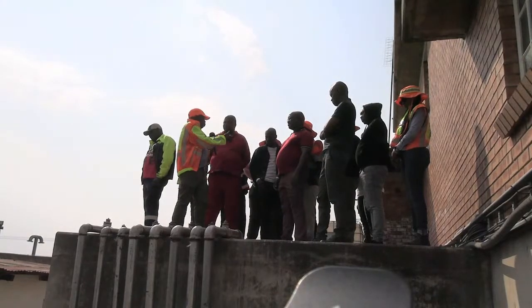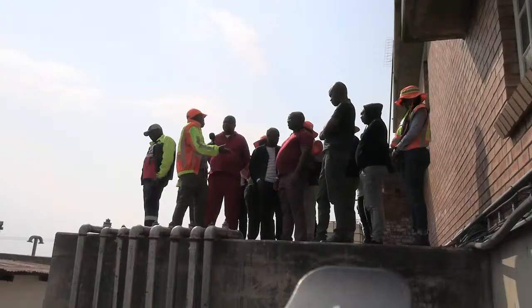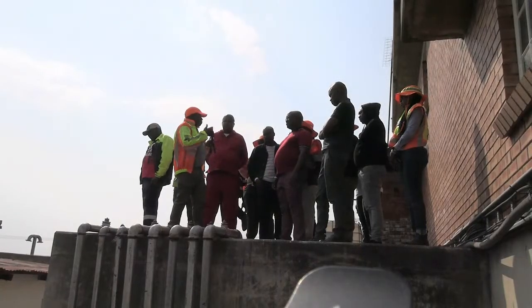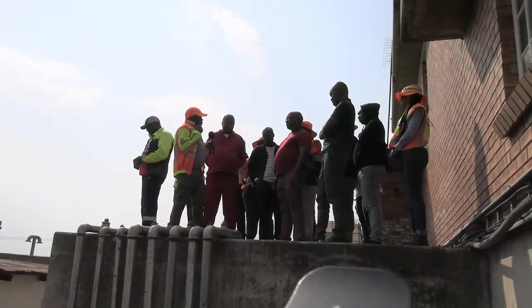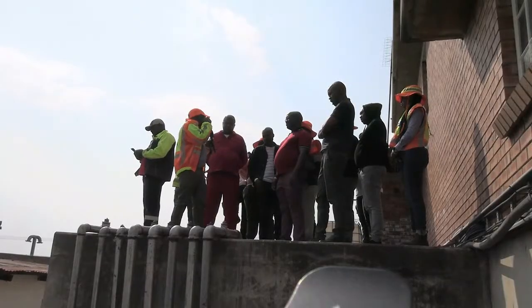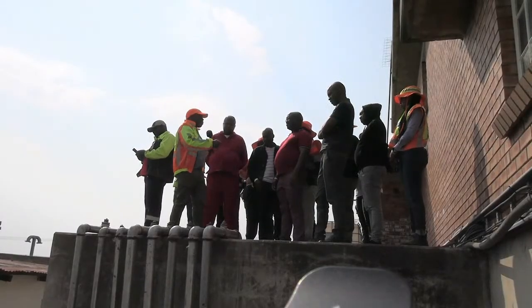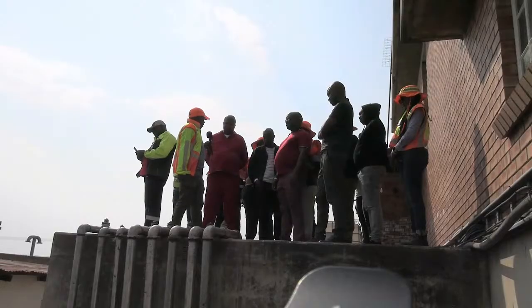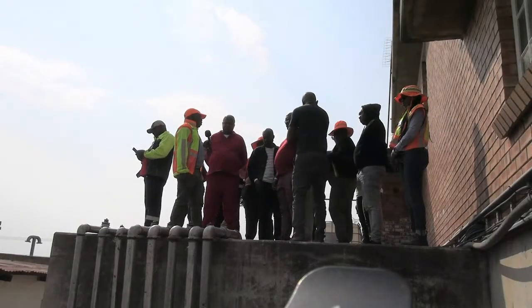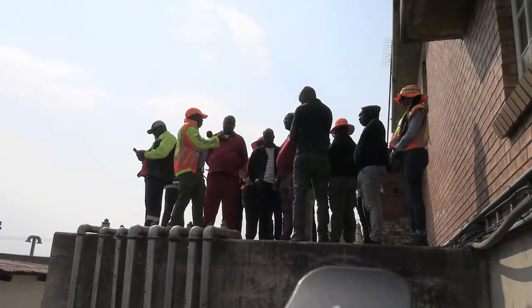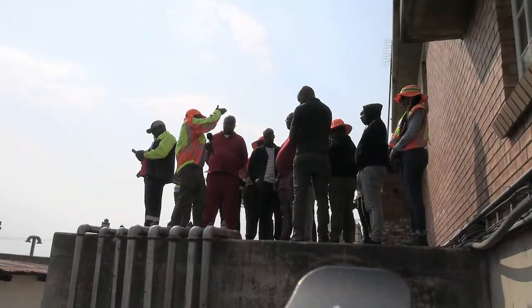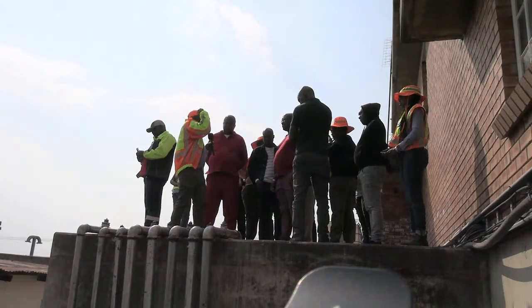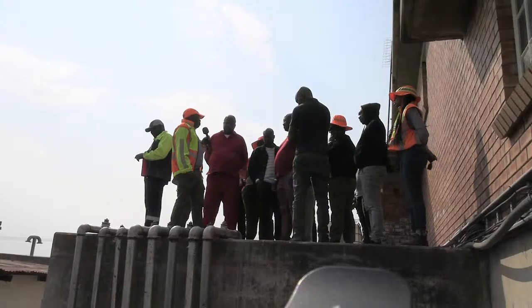This was a problem because of the demand the municipality has against what they are paying. So in future when we do this, the transformer is here, but we'll have to go and pay for the maximum notification of electricity. We're no longer using 300 kVA, but we'll use plus 500 kVA, so you need to go and notify the maximum demand.